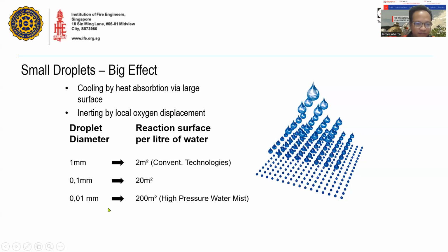Now, that 0.1 mm droplet will be lessened even further to 0.01 mm. And that means you are introducing a higher pressure. There will be 200 square meters of high pressure water mist coverage. If you see from the figure itself, that's literally how it is being explained. So the smaller the droplet diameter and the higher the pressure you apply, the bigger the surface area being protected, the bigger the surface area of heat absorption, and the bigger the surface area of inerting, the local oxygen displacement.